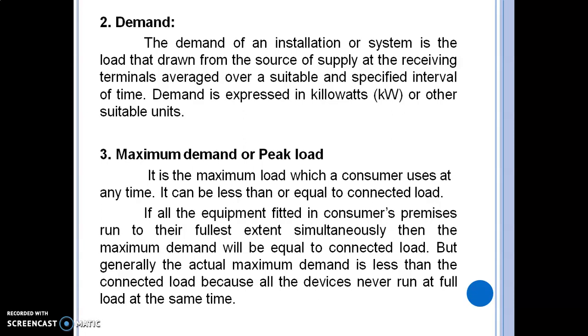The maximum demand, or peak load, is the maximum load which a consumer uses at any given time. It can be less than or equal to the connected load. If all equipment in the consumer's premises runs to its fullest extent simultaneously, then the maximum demand will equal the connected load. But generally, the actual maximum demand is less than the connected load because all devices never run at full load at the same time.